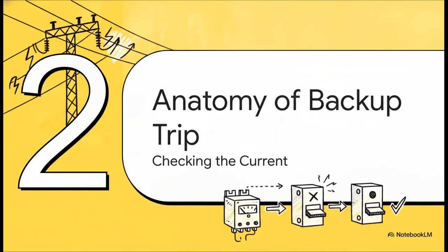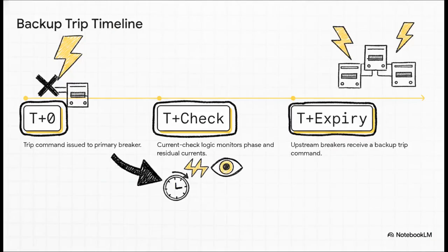Moving to Section 2, anatomy of a backup trip. Checking the current. So how exactly does the relay know a breaker has failed? Well, it all happens in a very precise chain reaction. At T0, the relay issues a standard trip command, but it doesn't just assume the job is done. Instead, the relay's current check logic actively monitors the phase and residual currents, and it starts a timer. If that timer expires and the relay still sees fault current flowing, it knows for sure the primary breaker failed, and it instantly fires a backup trip command to the upstream breakers.